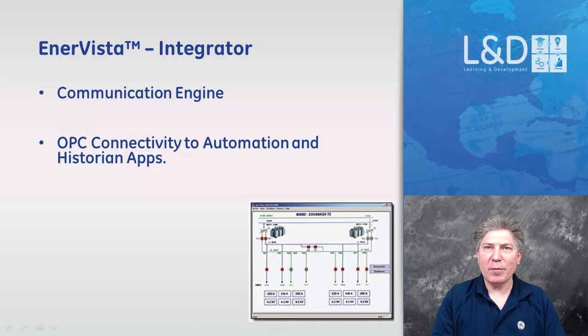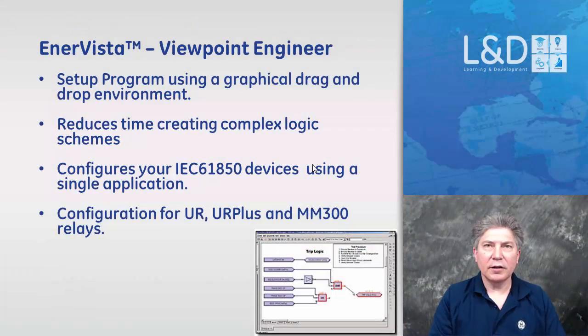With tested pre-configured memory maps for Multilin devices, EnerVista Integrator eliminates the significant effort required for programming of all the mnemonics associated with HMI, SCADA, and DCS system integration, greatly reducing the commissioning time and cost of an OPC server. So the Integrator is basically the engine that is being used in Viewpoint Monitoring. So once again, in Viewpoint Monitoring, we were having all the data being extracted from the individual relays, and the Integrator is the actual engine in the background that's pulling all the data.